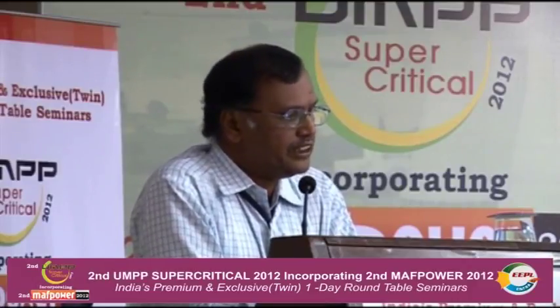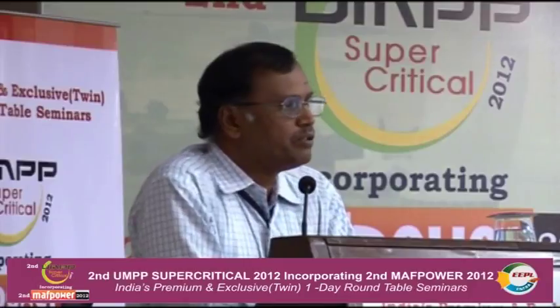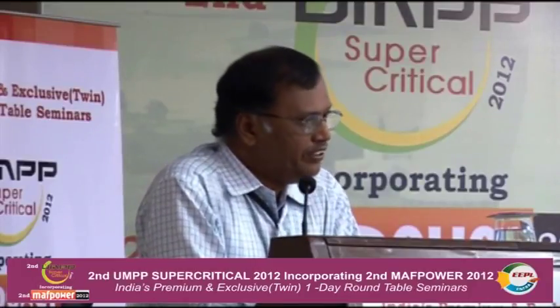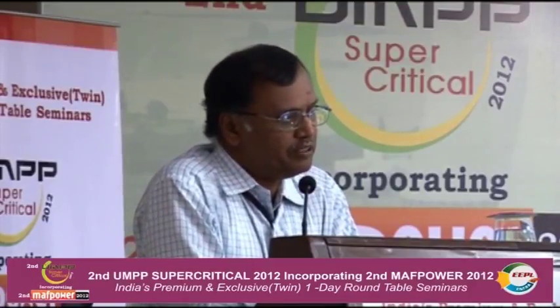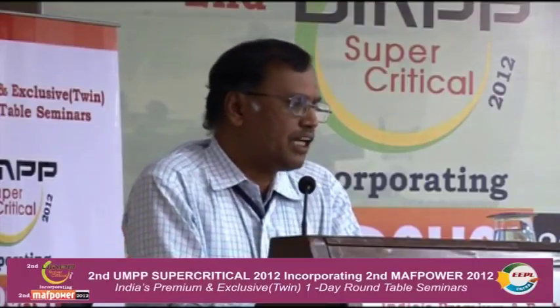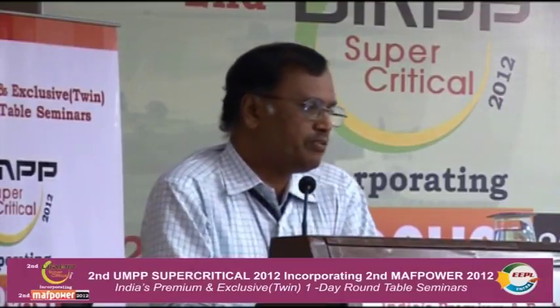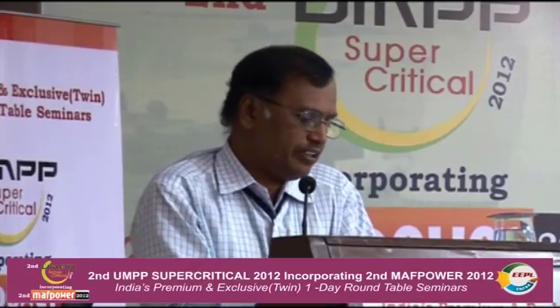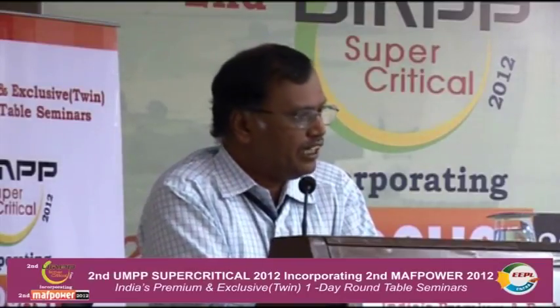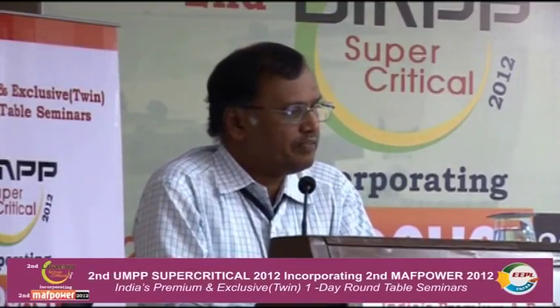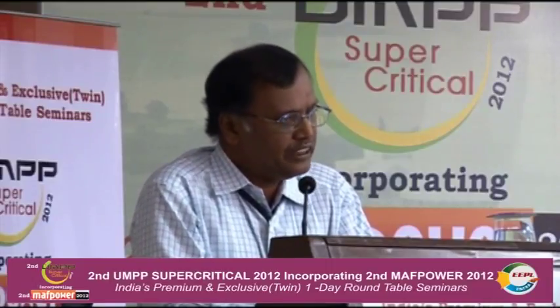And we are giving a tilting tangential firing system, which is proven technology for the past half century. Our boilers will be dry bottom with balanced draft. Since the number of mills happens to be more than 8, it is always preferable to locate them on both sides of the boiler. This is our standard feature. And nowadays mills are coming with improved wear life. So the performance of the mill has improved compared with the late 70s.